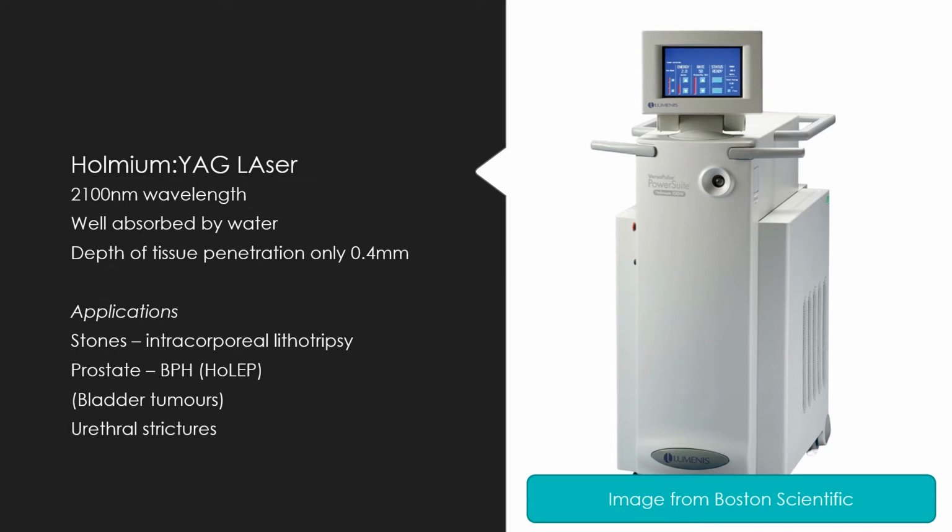It is used widely in urology theatres, and I'm sure most of you have used it at some point in your training. We've already looked at its wavelength, which at 2100 nanometers places it in the near to mid-infrared spectrum. It is avidly absorbed by water and consequently only penetrates to a depth around 0.4 millimeters in tissue, making it relatively safe to use in the ureter and in the kidney.